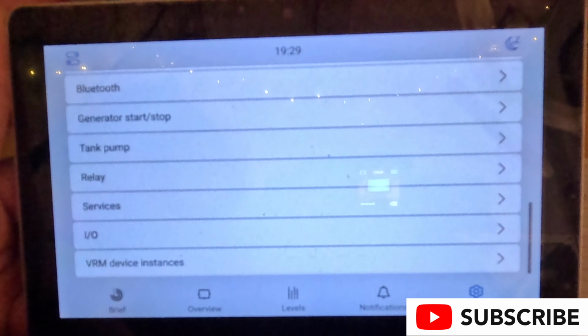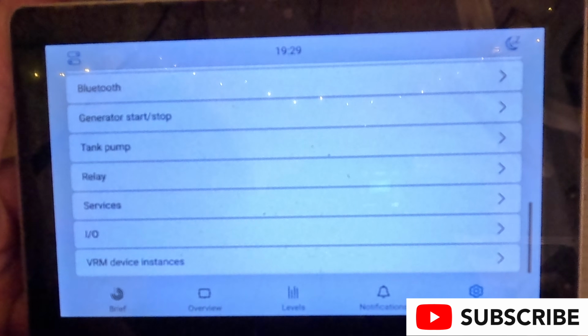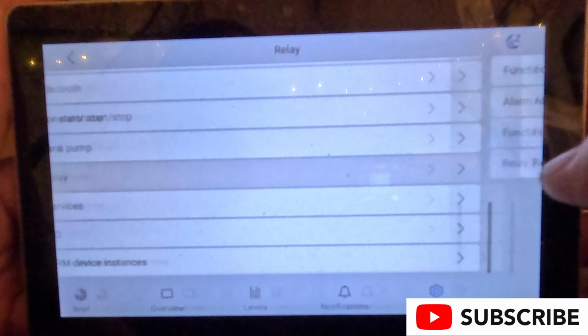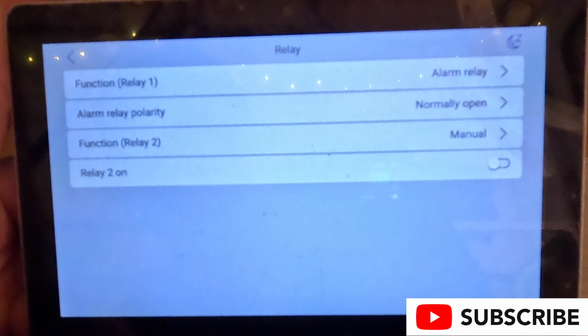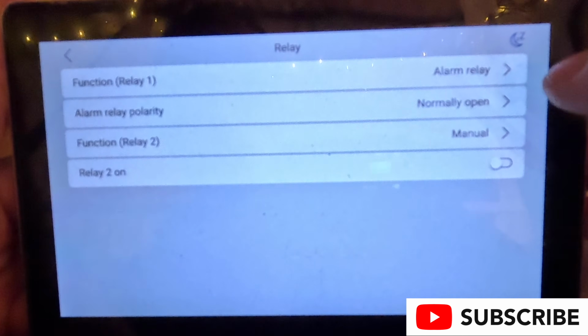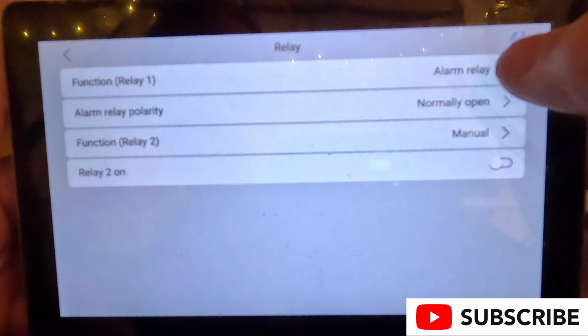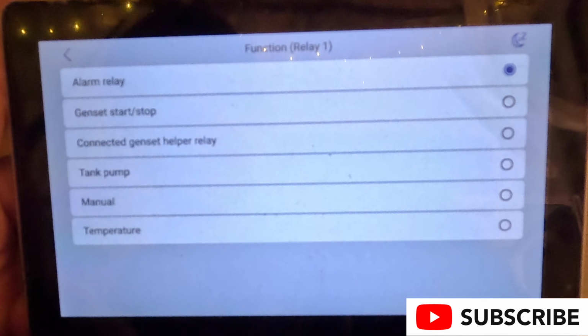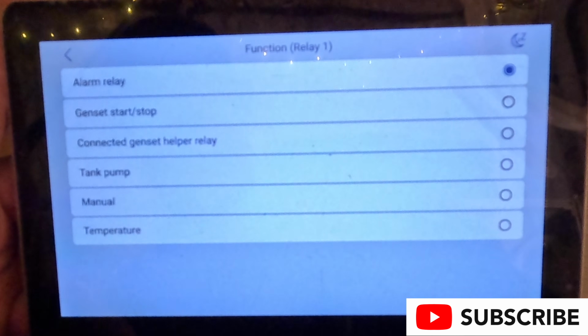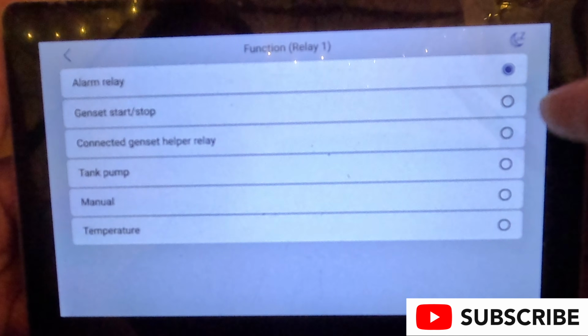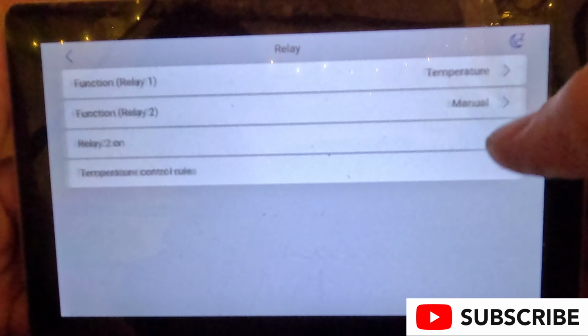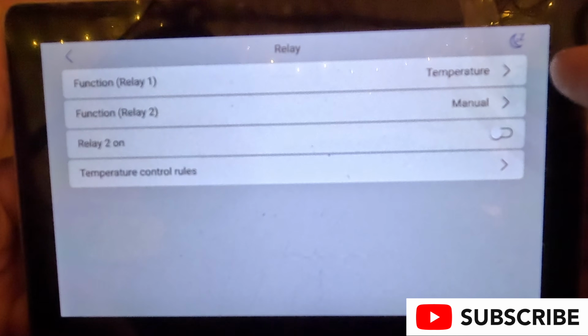We back out two times and go to a different spot in the menu, the relay location, where we're going to turn on relay 1. By default it's on this alarm relay, but we're going to change that. You can see alarm relay, genset start stop, connected genset helper relay. We're going to put it on temperature.